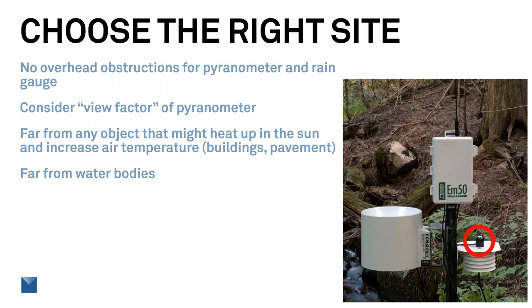Getting back to the virtual seminar, you want to consider the view factor of the pyranometer, and also if you have a pyrgeometer for long wave radiation or net radiometers, typically those have a hemispherical or 180 degree field of view. So if you have any trees or buildings poking up into that hemispherical field of view, they'll be in the view factor and can cause bias and error. You want these instruments exposed to open sky.